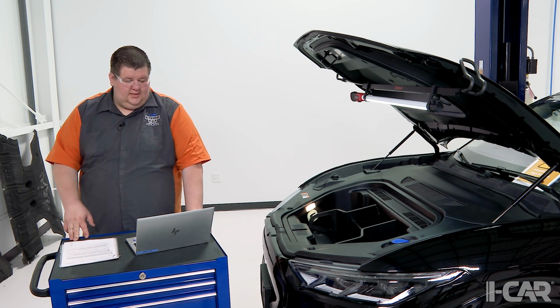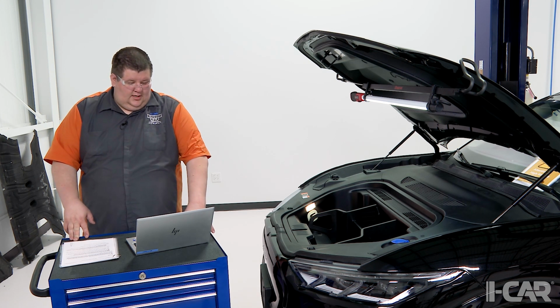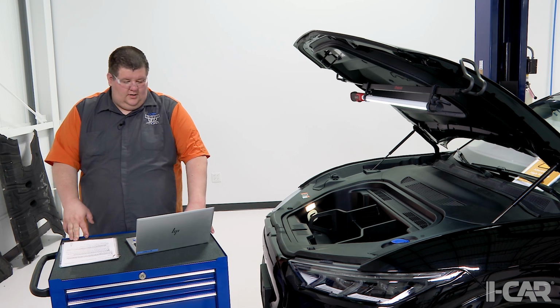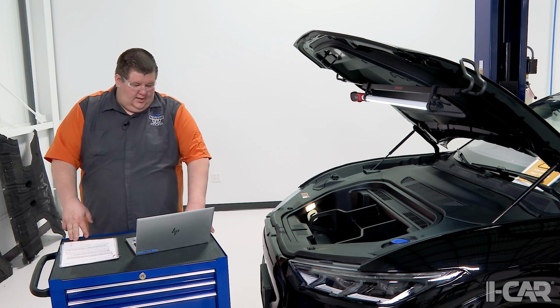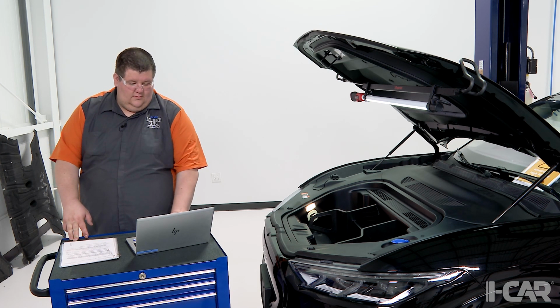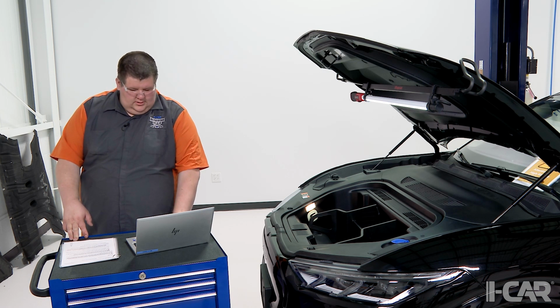It's doing an isolation resistance check. Any value below 206.4 kilo ohms is considered to be a mild isolation fault. We are currently at 492.2, so we are good there. Continue on - it's going to then continue through.